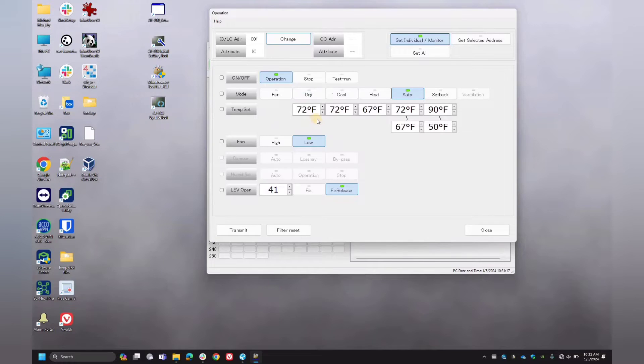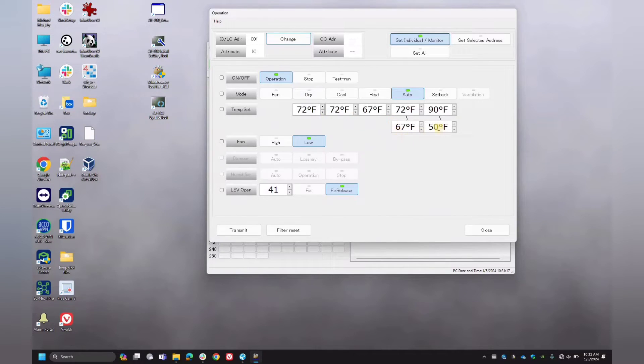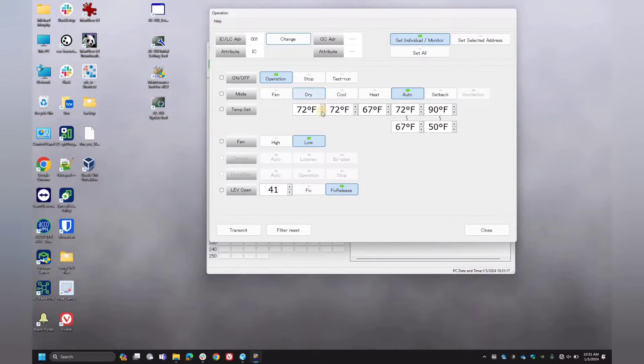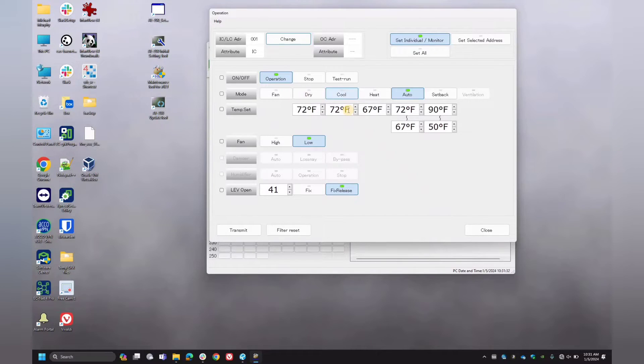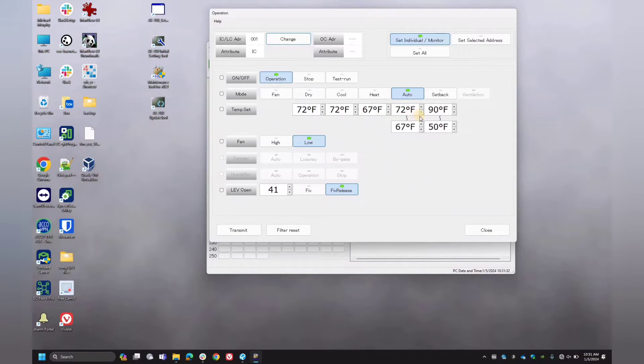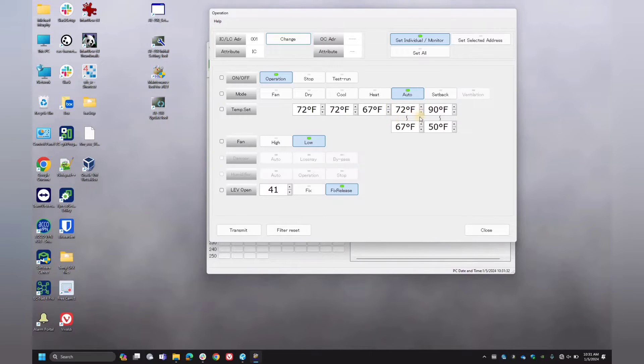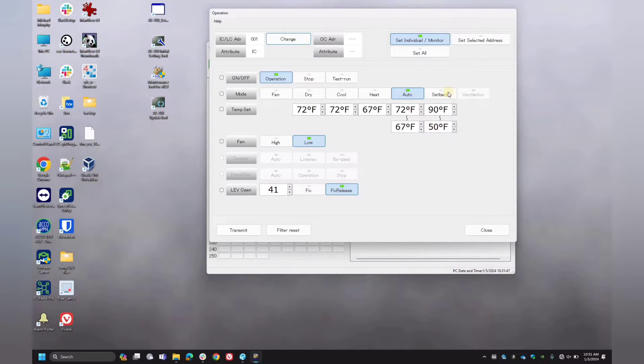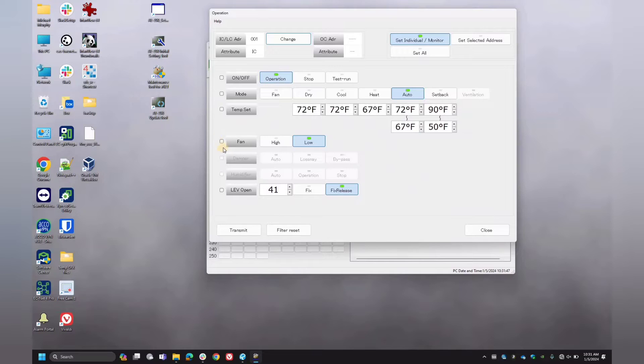Here, as you can see, we have various amounts of set points with this device that's already been pre-configured. You can see here it has a temperature set point for its dry mode, its cooling mode. We have the set point there, the heating mode, and for the auto mode. This here would signify your cooling. So this is your upper limit for cooling. And then you can see here it's linked to a lower limit, which is your heating set point. And then your setback set points are right here.